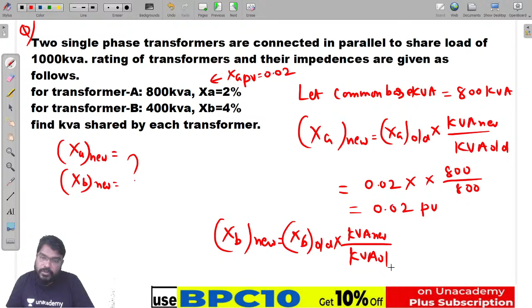Next, XB new per unit value is equal to XB old into kVA new divided by kVA old. XB old is 0.04 into kVA new, which is 800, divided by 400 kVA. So now it is equal to 0.08 per unit value. So these are the XA new and XB new values.